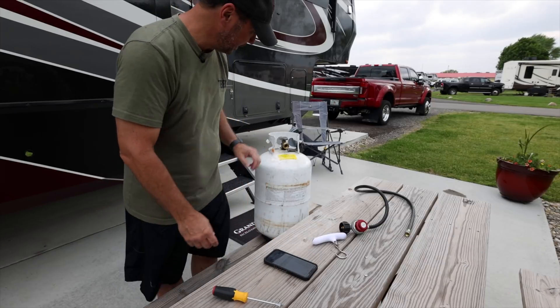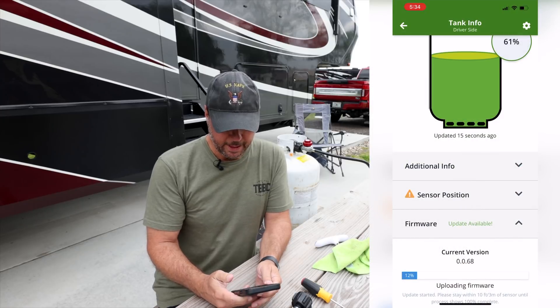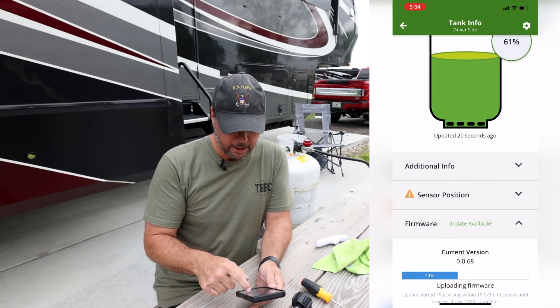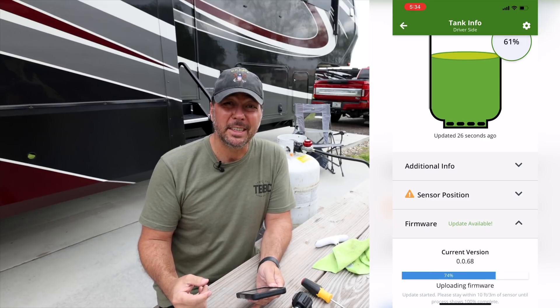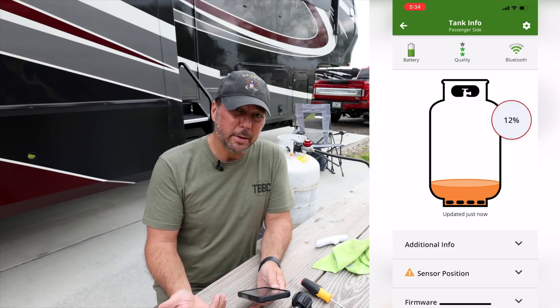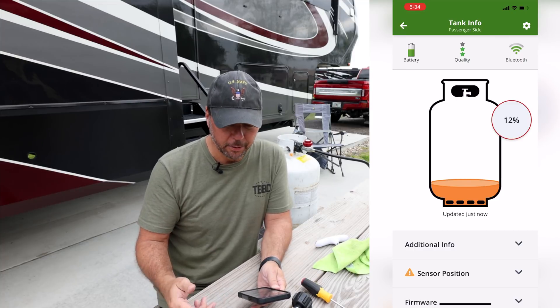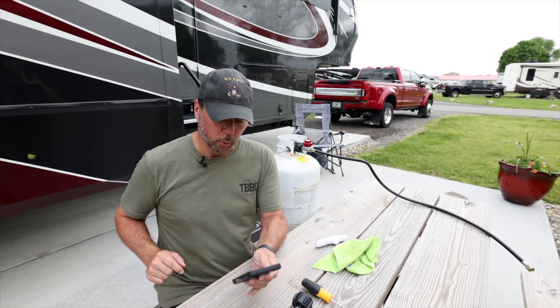Let's bleed it down to 10% — we're almost done. I noticed at the bottom of the screen there was a firmware update available, and I updated it wirelessly over Bluetooth — super easy. I'd never seen that before on these pro sensors. Now it's reading 12%, so maybe they fixed something in the firmware at lower levels, or maybe it just settled down. I'm going to continue bleeding to get to 10% and then take another weight measurement.